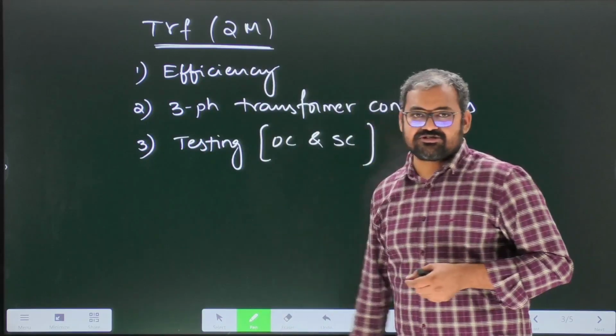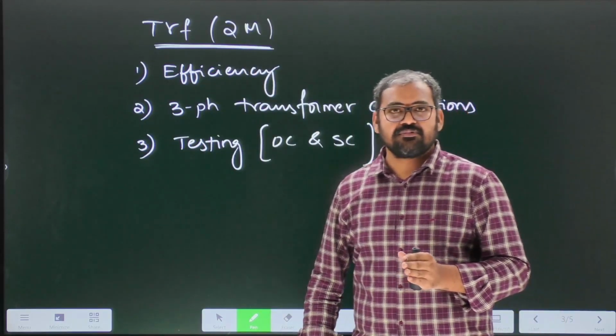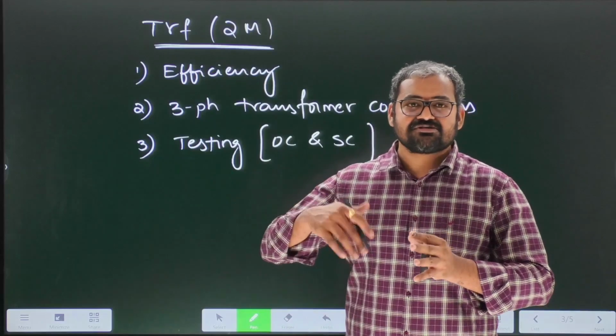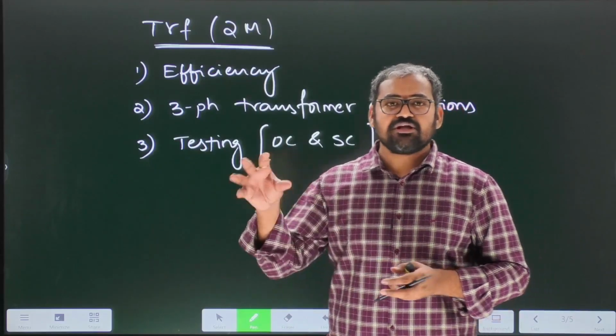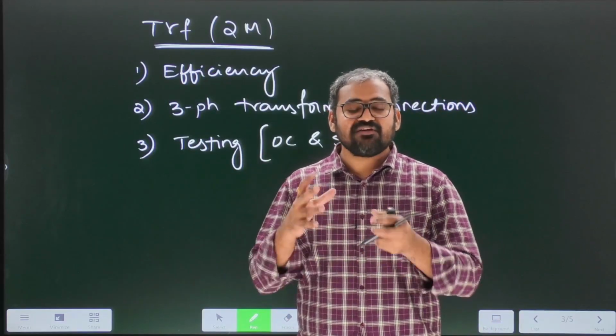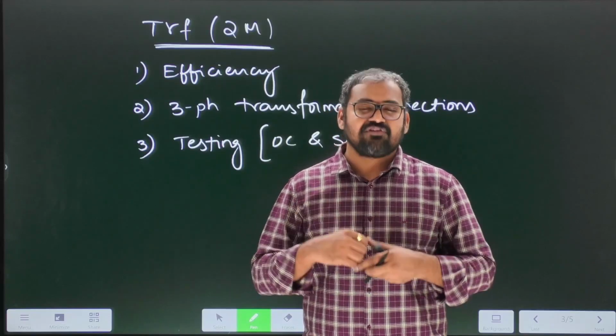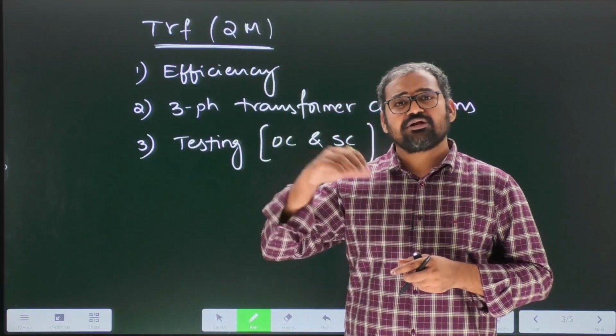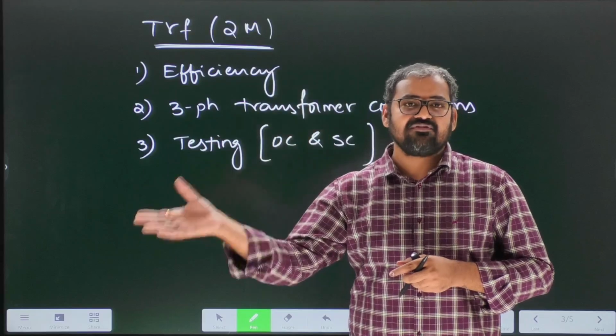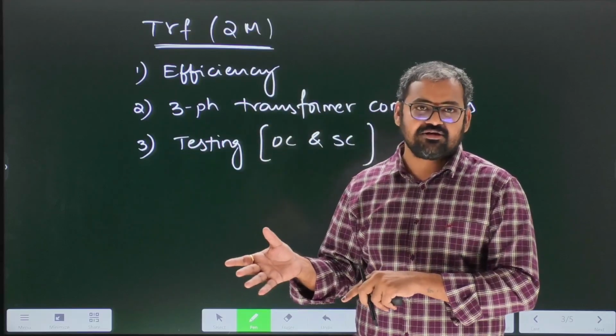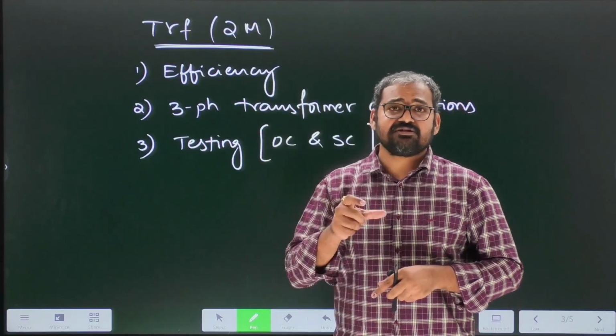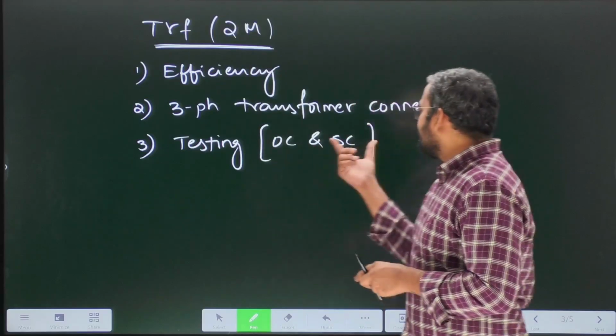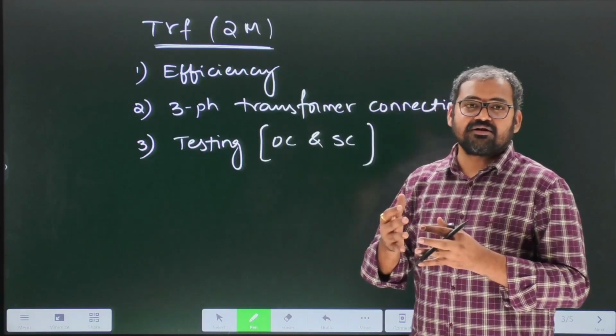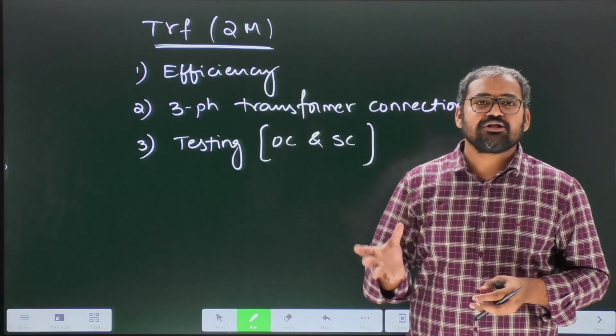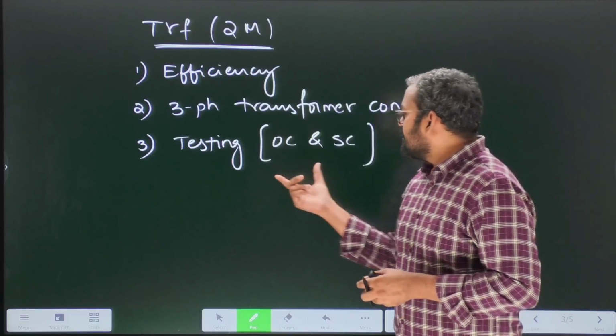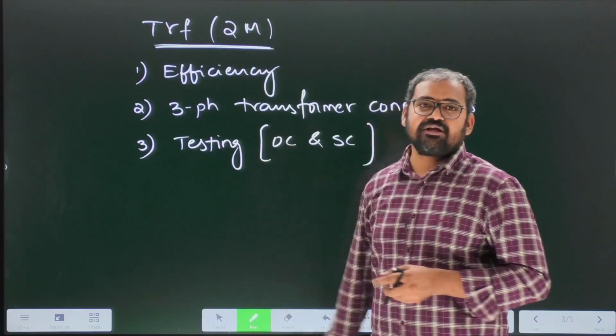Questions will come from these two testings. What is the purpose of the OC test, and what are the conditions during the OC test, is voltage, current, or frequency the rated value? What losses can we find from that test? How to transfer parameters of the OC test from LV side to HV side or vice versa? What is the equivalent circuit during the OC test? Similarly for the SC test: what is the voltage condition, current condition, equivalent circuit, and per unit Z calculations? This is the third most important area you have to focus on.